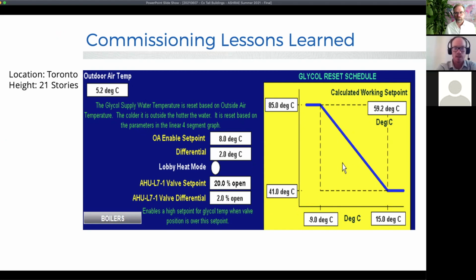It had revolving doors and some man-leaf doors too, but what they tried to do on their own you can see by this graph, for those who prefer Fahrenheit. We're close to freezing temperature, 5.2 degrees Celsius outside air, so not terribly cold. But what they'd actually done to mitigate this is set it so that glycol reset schedule would be negated entirely if the air handler serving the lobby had its heating valve beyond 20% open. So if it went beyond 20%, they just went straight to 85C water, which of course made everybody else in the building quite warm.